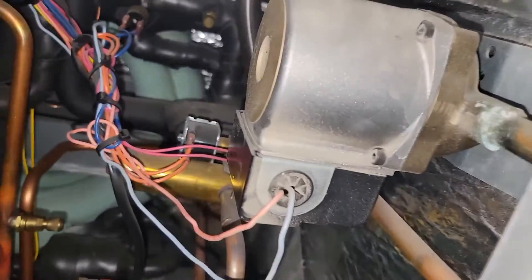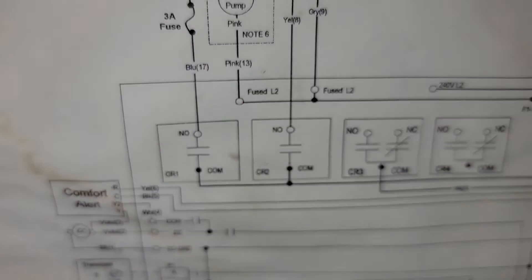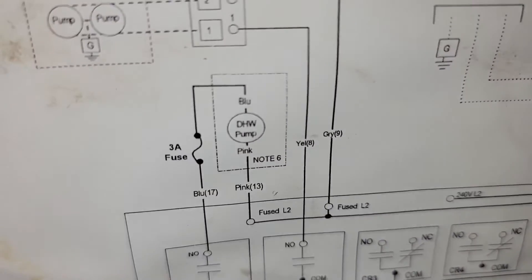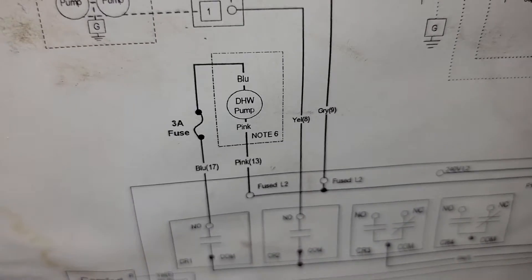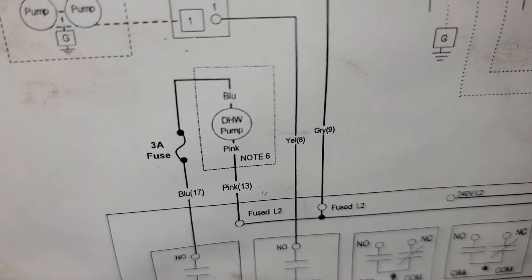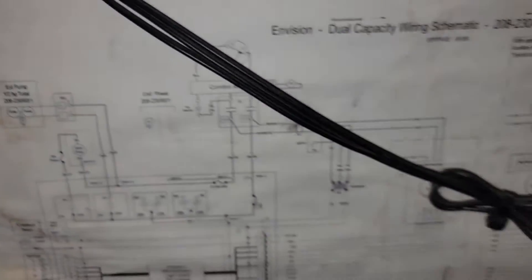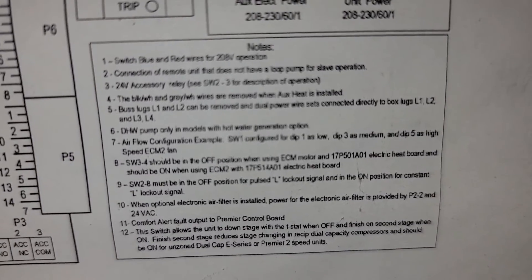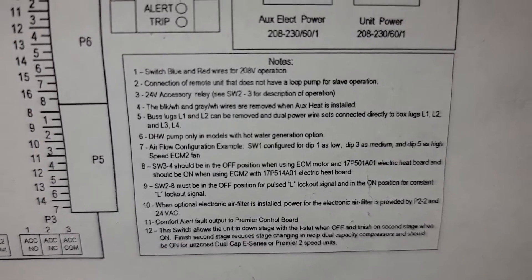If this loop was being used, then you would also use this pump right here. On the schematic, this pump would be controlled with relay CR1, and there's an inline fuse as well to protect against a power or pump issue.